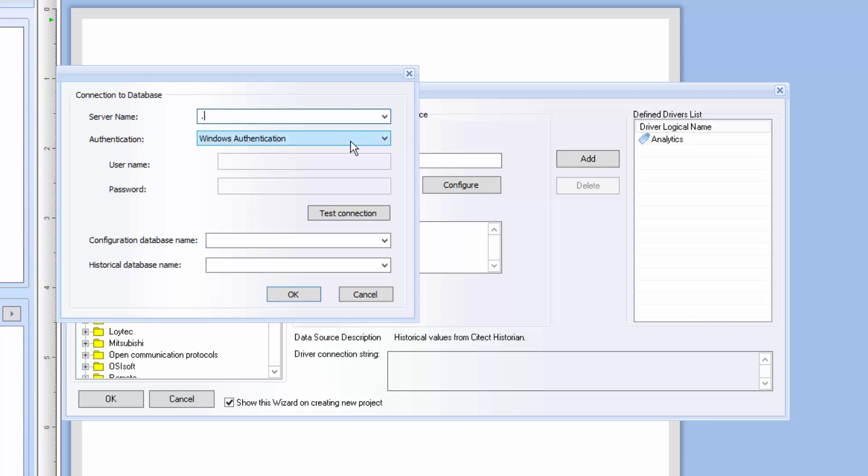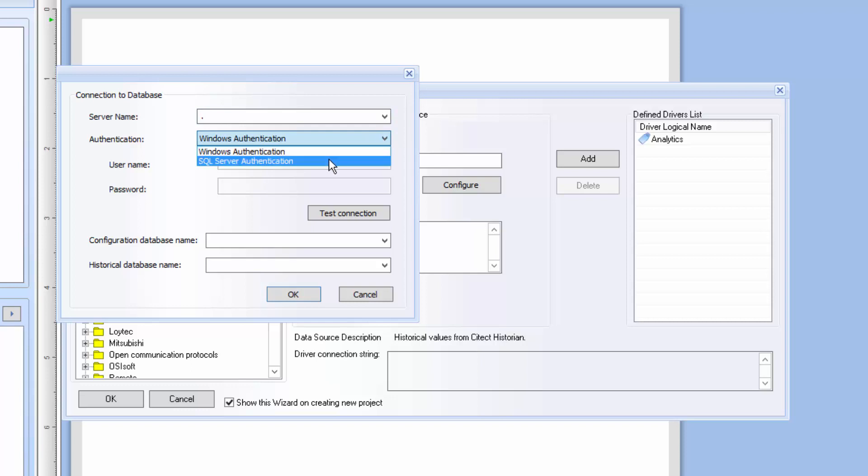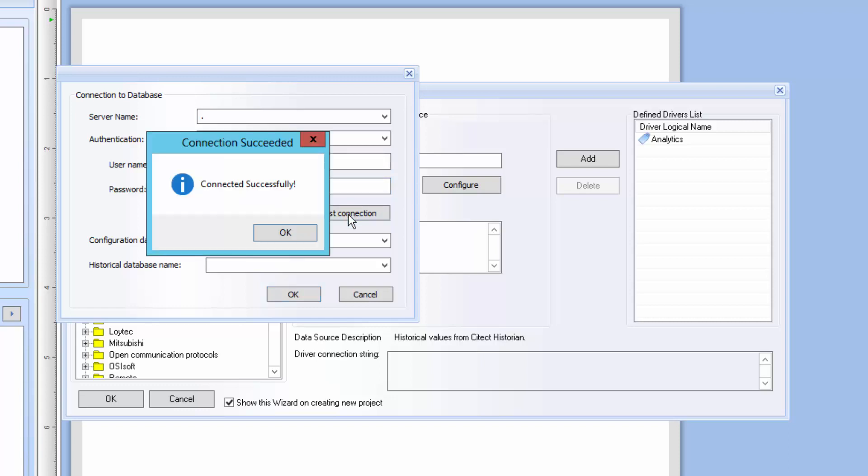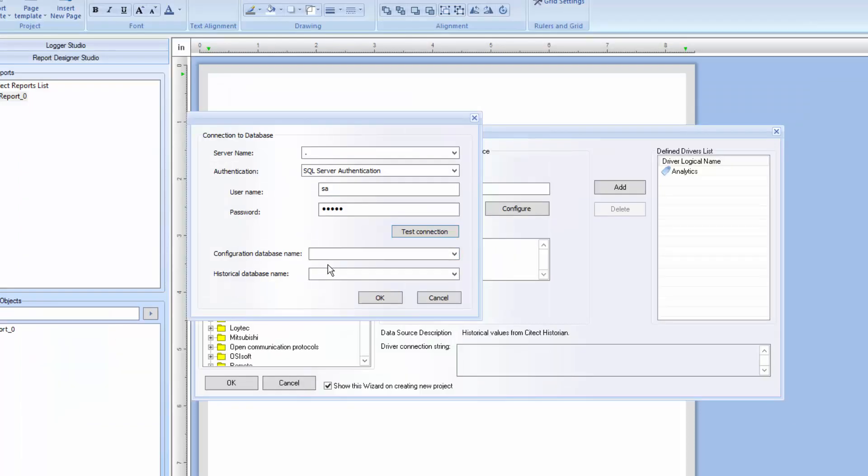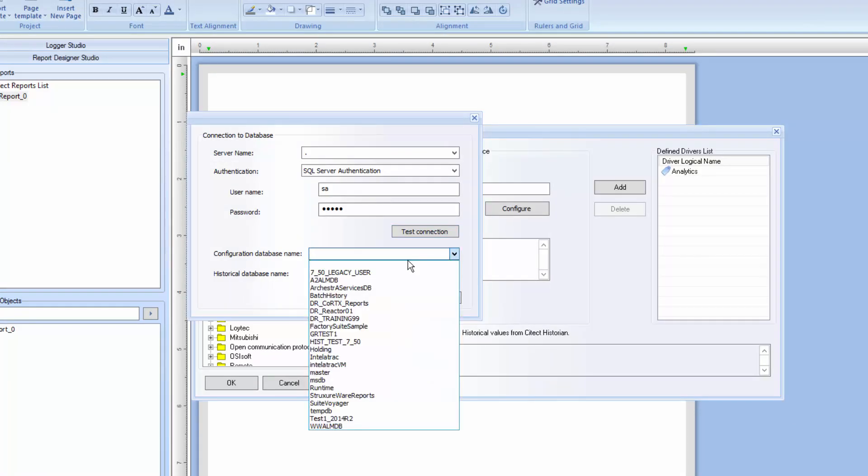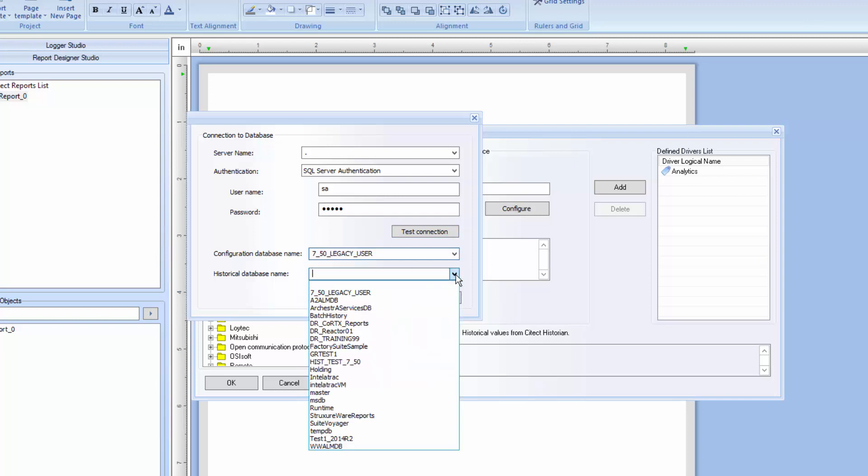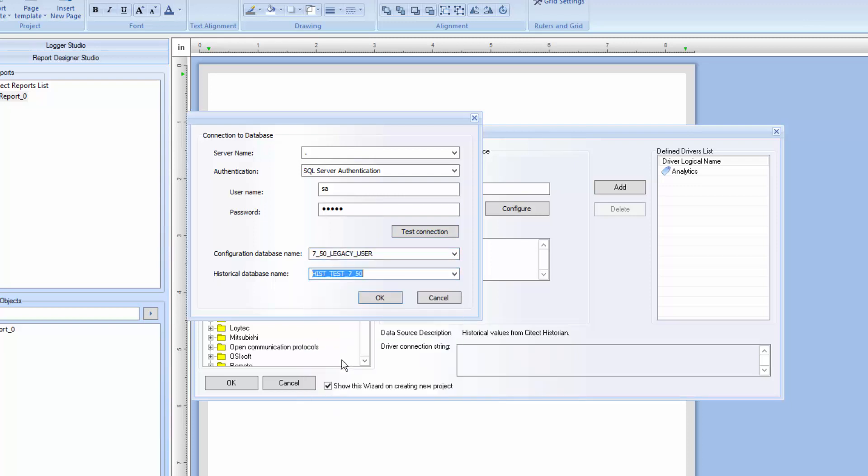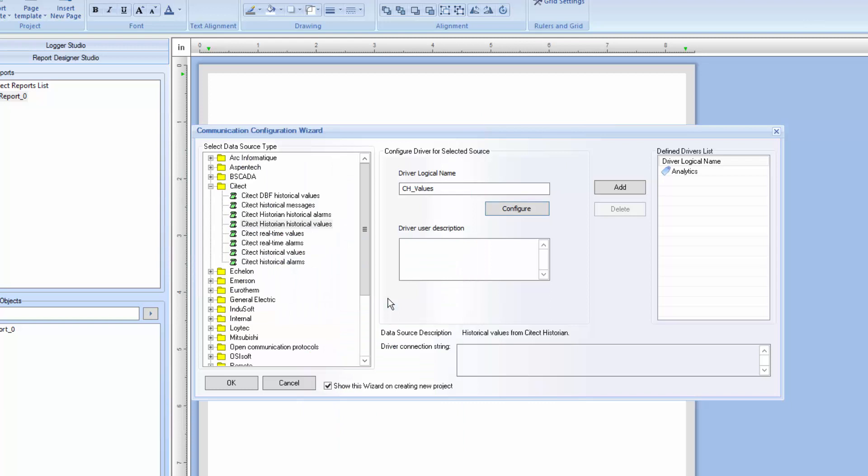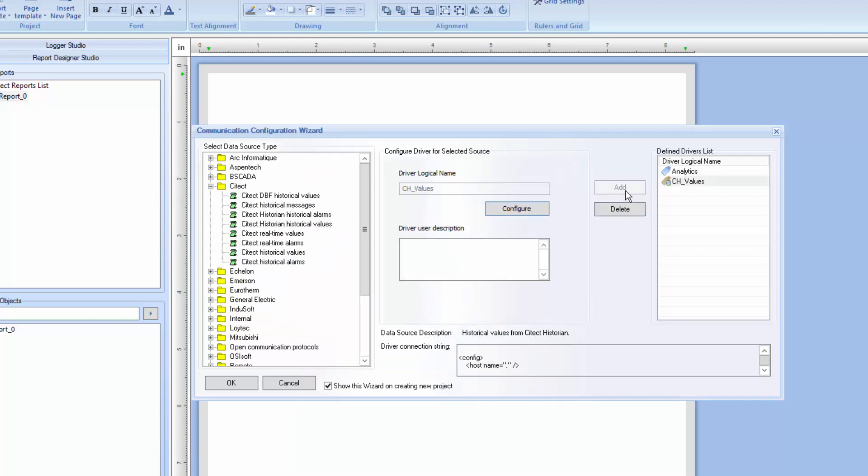Next, we'll select the SQL Authentication mode, either Windows-based or SQL-based authentication. I'll use SQL-based here. Let's test the connection before we continue. Finally, we need to select the Historian's Configuration database and the Historical Data database name. Click OK and then add the configured driver to the list.